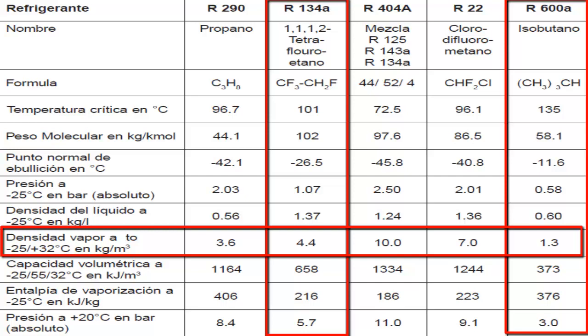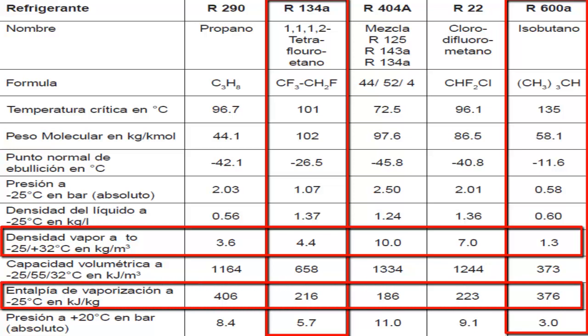In contrast, R600A is less dense, resulting in a lower flow of grams through the compressor. However, each gram of R600A has a higher cooling capacity, which compensates for its lower density.